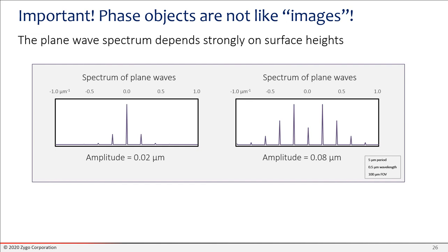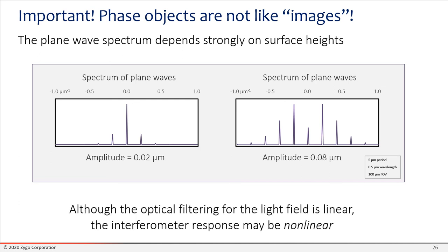It's quite important to realize that phase objects, that is, like topography objects that create this phase shift, are not like images. The plane wave spectrum strongly depends on the surface height. So here's an example where you have a sinusoid. It's the same period sinusoid in both of these graphs. The difference is the amplitude of the sinusoidal topography feature, and you can see for a larger amplitude you get many more diffraction orders. And all of these diffraction orders have to be captured by that partially coherent transfer function to get good linear results. So even though the transfer function for the light field is linear for a wide variety of circumstances, the interferometer response may be non-linear. And that's one of the reasons why you want to do modeling is to find out when it might be non-linear.